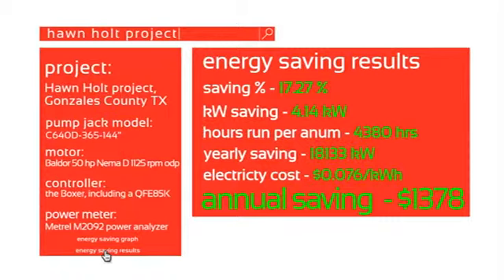Typically this pump jack runs for 4,380 hours per year. So the yearly energy saving was 18,133 kilowatt-hours, and at an electricity cost of $0.076 per kilowatt-hour, the annual saving was found to be $1,378.